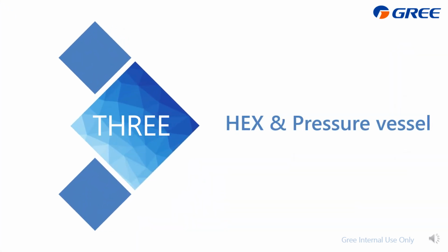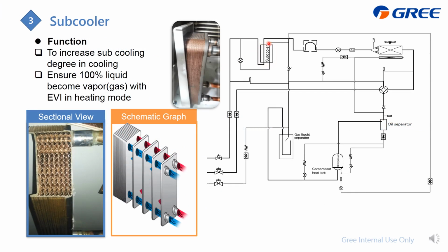Next chapter, we will go to the heat exchanger and pressure vessel. Subcooler located here just after the IPN cooler and the outdoor heat exchanger, and here is the appearance. From this working graph, you can find that this is the plate on the left side and right side. They are just two different flow, and we just make them to make heat exchange inside. From this sectional view, you can find that this is actually the inside plate. It is not flat. We make it to be uneven to higher the heat transfer efficiency.